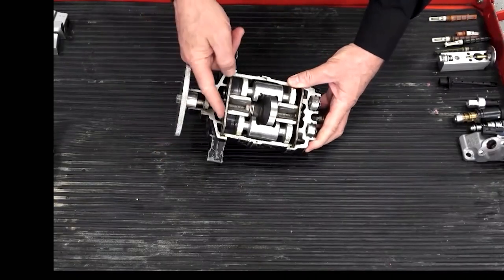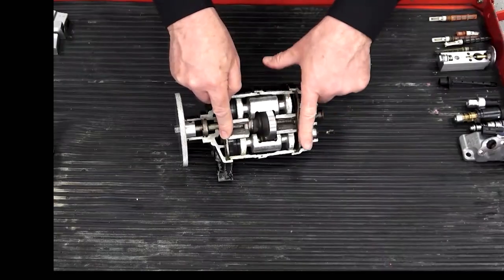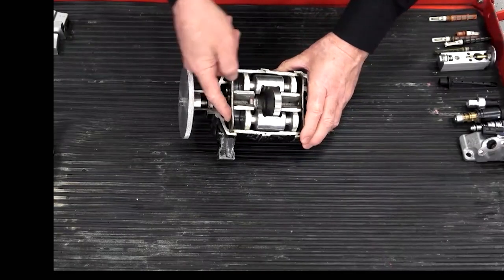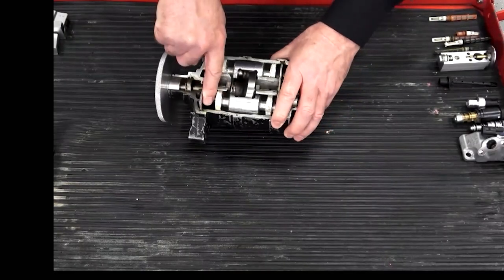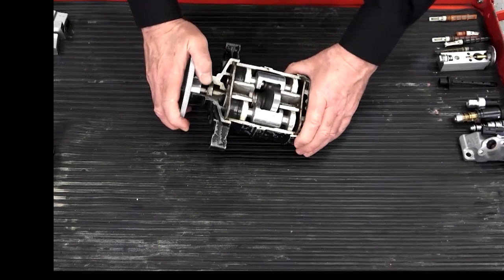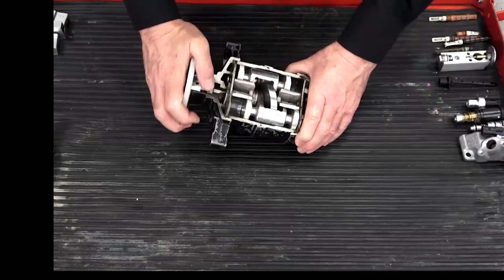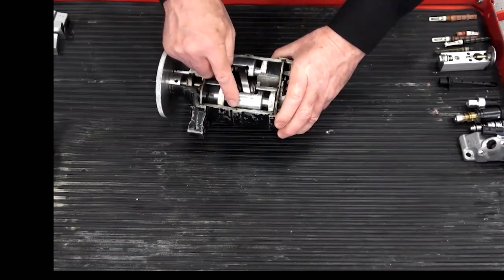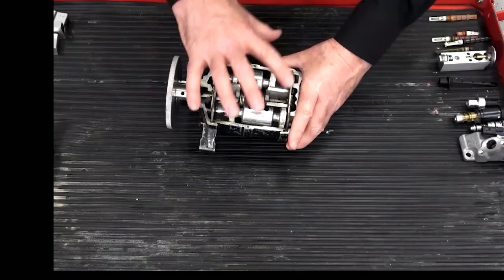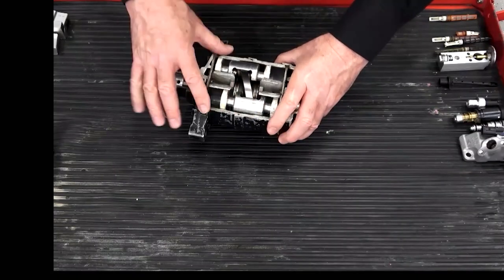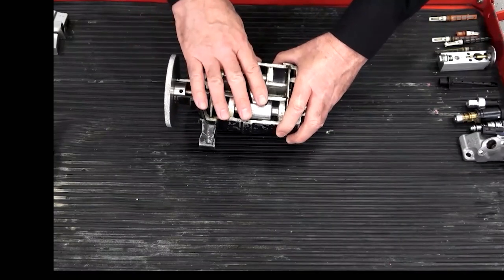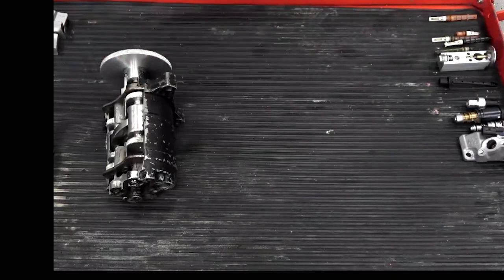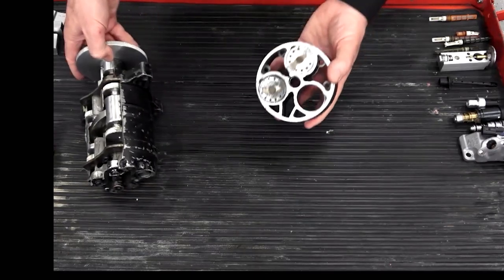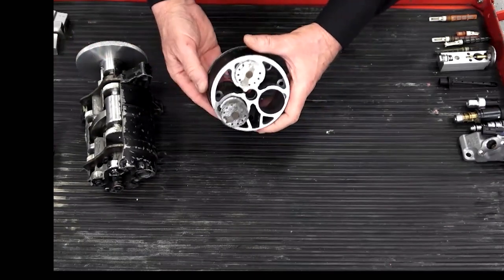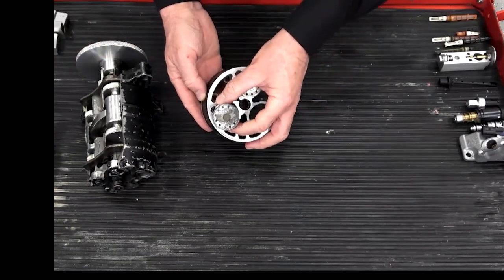The original ones had reed valves on the valve plate here, a discharge reed valve on this side of the plate, and a suction reed valve on the inner side of the plate. And that piece of it worked pretty well. The problem is they used three big O-rings and they didn't use locating dowels between the cases. So these are pretty prone to leak. Now, that design was redesigned. I wouldn't call it an upgrade exactly. I think it was a cost-saving effort.